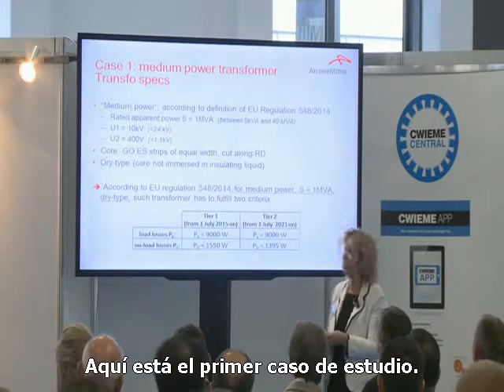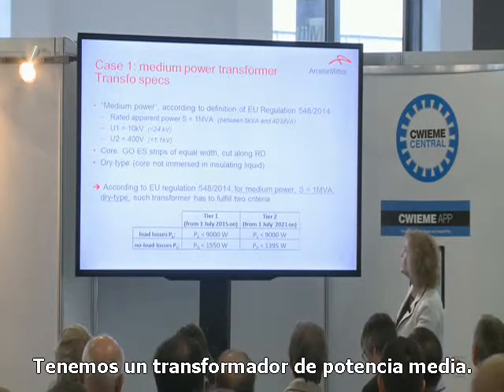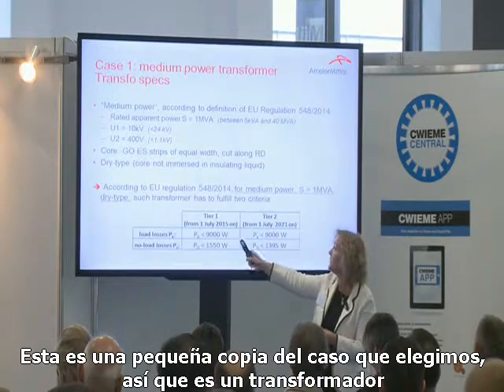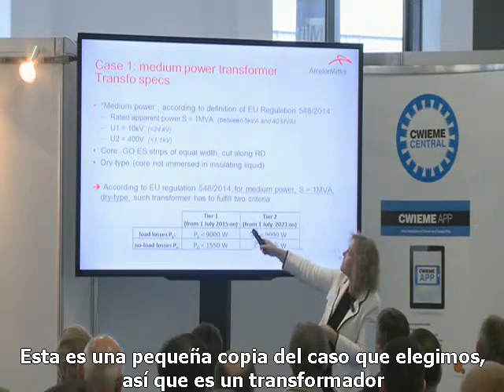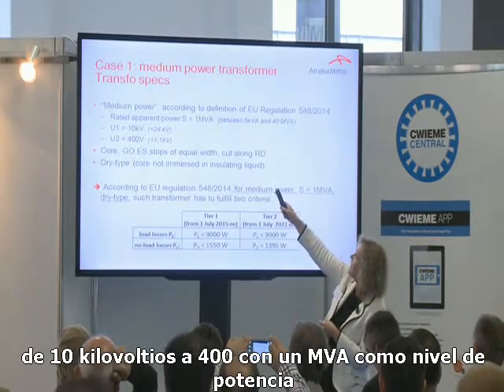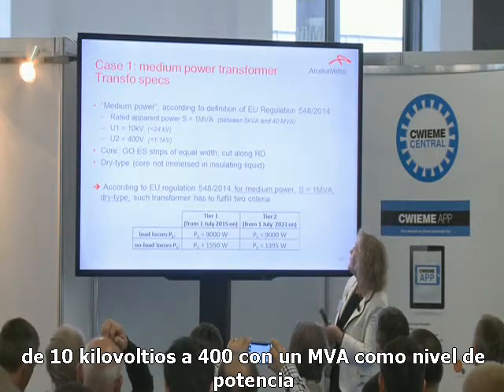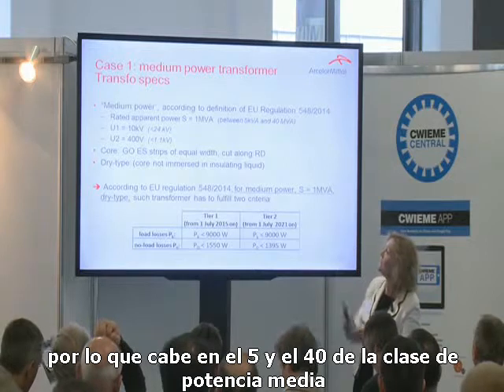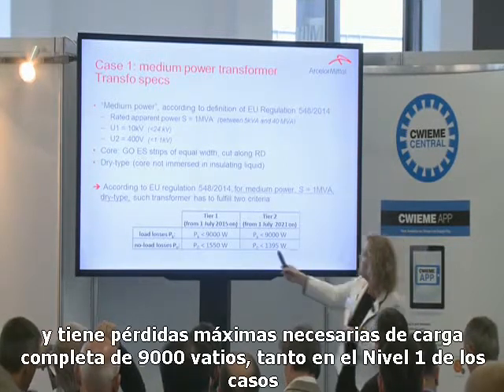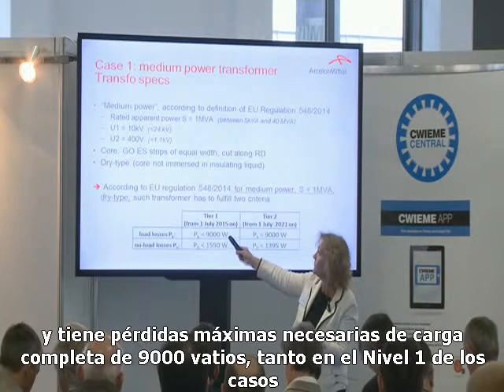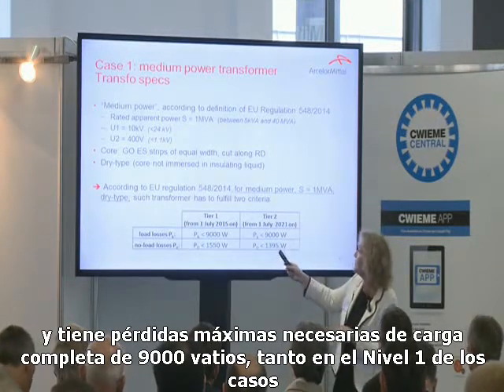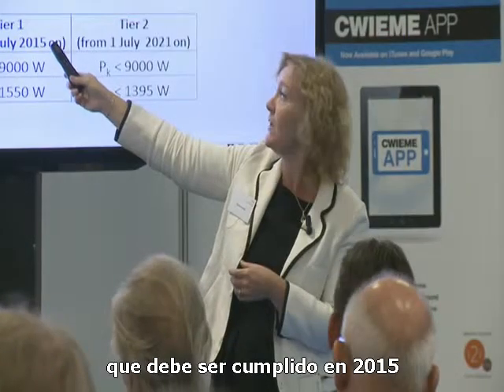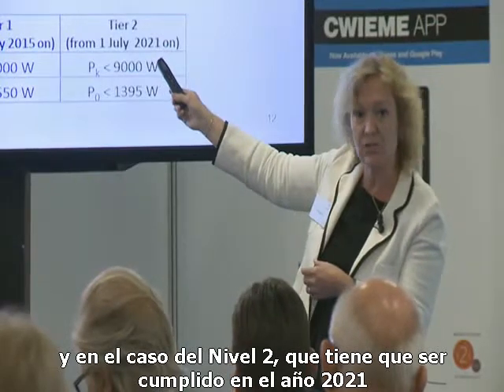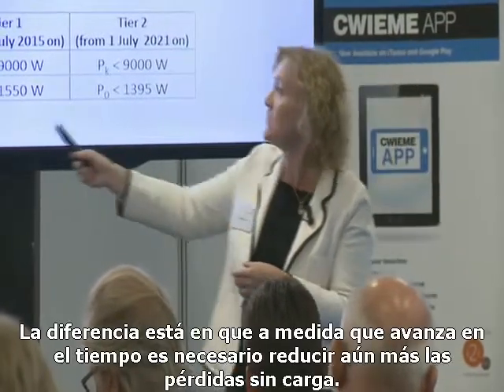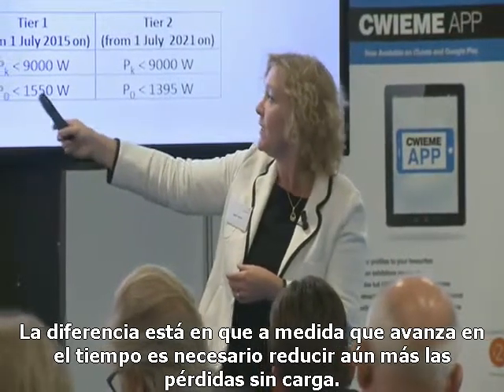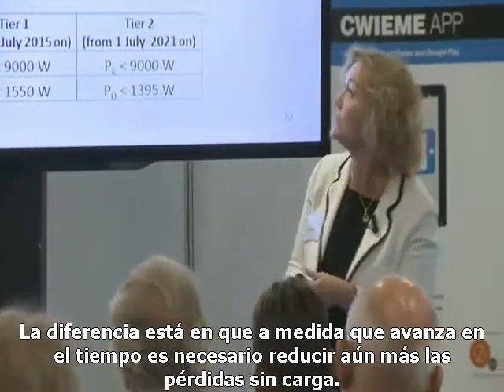Here is the first case study, regarding the medium power transformer. This is a small copy of the case we chose: a 10 kilovolt to 400 volt transformer with 1 MVA power level, which fits between the 5 and 40 of the medium power class. It has a necessary maximum full load loss of 9,000 watts, both in the Tier 1 case, which needs to be satisfied in 2015, and the Tier 2 case, satisfied in 2021. The difference is that as you go along in time, the no-load losses need to be further reduced.